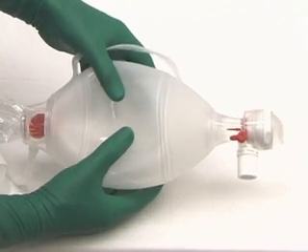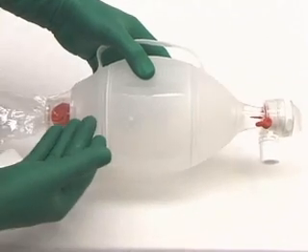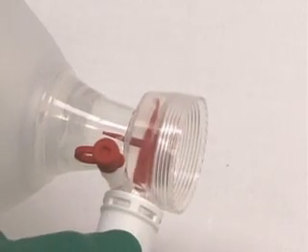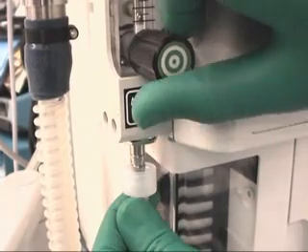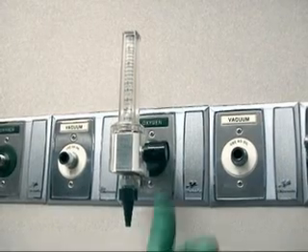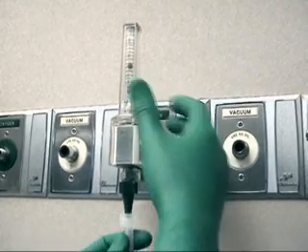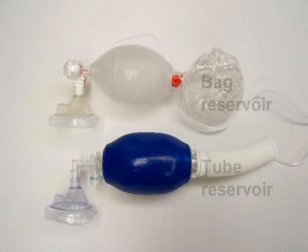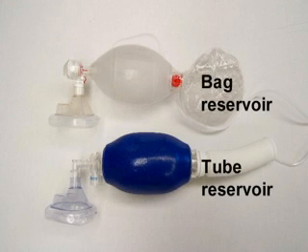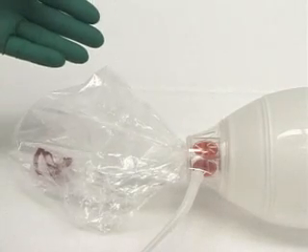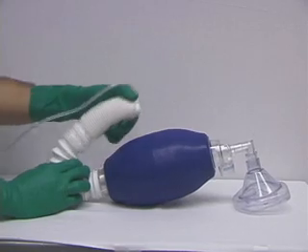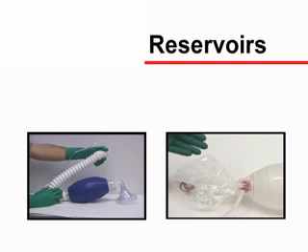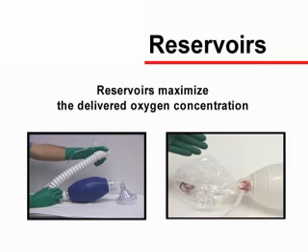There are a variety of bag valve designs available. All have a self-inflating bag and a non-rebreathing unidirectional valve, designed to function during both spontaneous and manually controlled ventilation. Because bag valve devices can operate without an oxygen source, it is important to ascertain that supplemental oxygen is flowing through the bag valve device when indicated and available. Bag valve devices can be equipped with an oxygen reservoir; if the reservoir bag fills, oxygen is flowing. The purpose of these reservoirs is to maximize the delivered oxygen concentration.